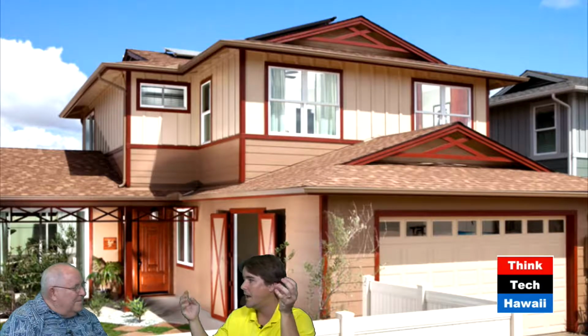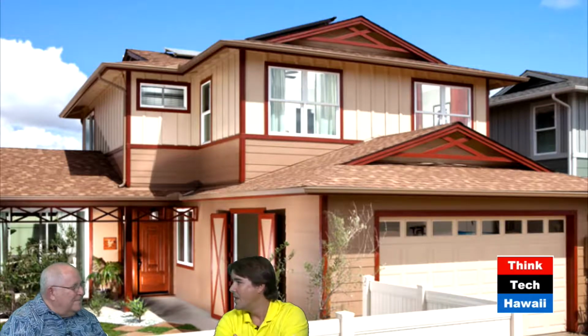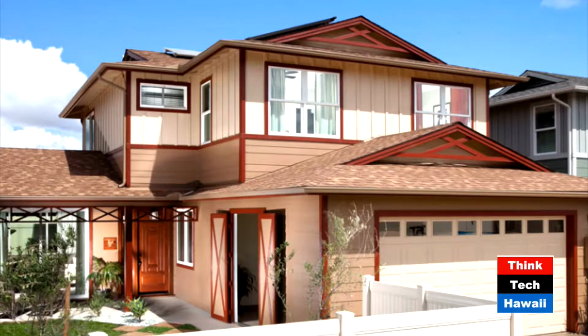And so any of the heat that would get into your attic doesn't, because it's insulated out. And so we let that be conditioned space. So if you go up in your attic, it's actually just as cool as the inside of your house. And that does two things. One, computers work more efficiently when they're cool, so do air conditioners. So if you can put the air conditioning equipment in conditioned space, they're going to work more efficiently. Two, if you have your ductwork in conditioned space, it's going to lose less heat. Just little things that all add up.